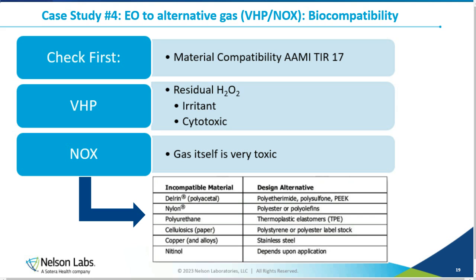For Noxilizer sterilization, the one thing we know is the gas is incredibly toxic. However, we also know it's a great method for sterilization because it doesn't leave concerning residuals. I think the biggest issue, which is what Jen talked about, is material compatibility. I just popped in this table from the standard TIR 17 that shows what materials are incompatible. And a lot of those are very common materials in medical devices: nitinol, polyurethane, nylon. So I think it's a limited window of materials or devices that could go to Noxilizer sterilization. But if you can, and it works with the other conditions that Jen was talking about, it seems to be a good alternate if it meets the needs.